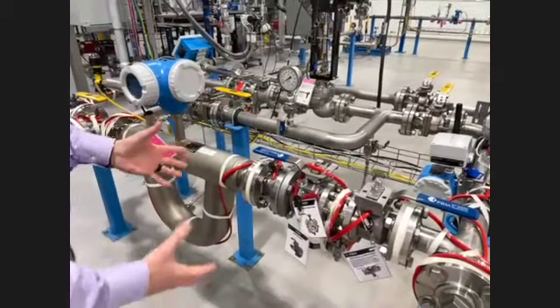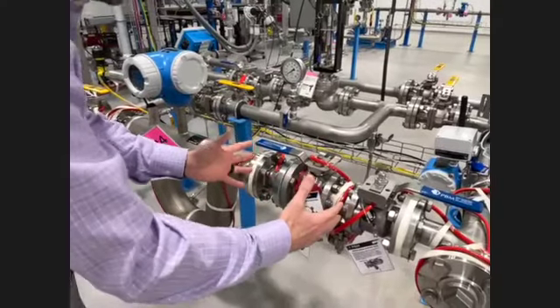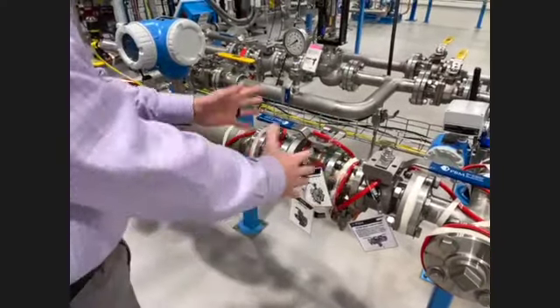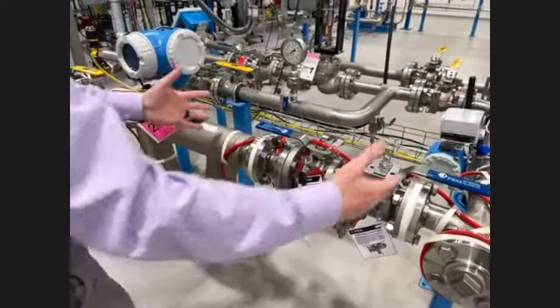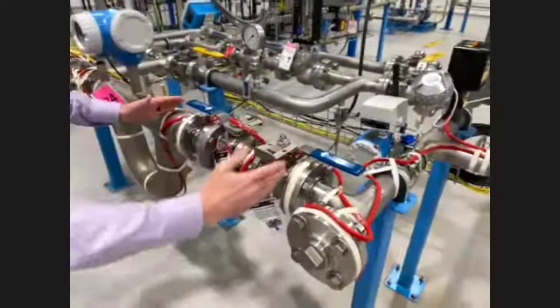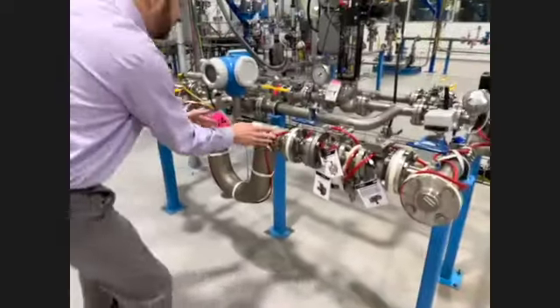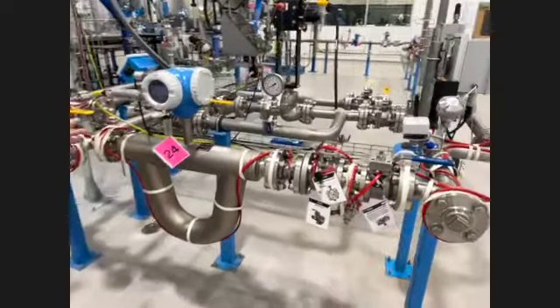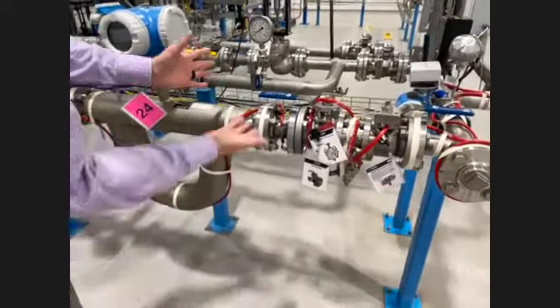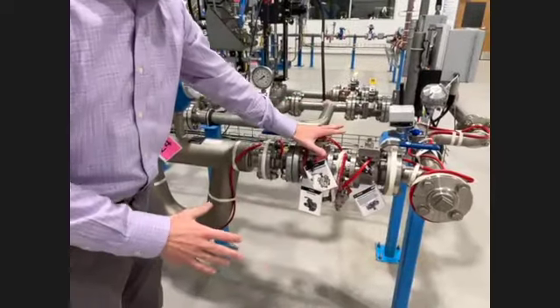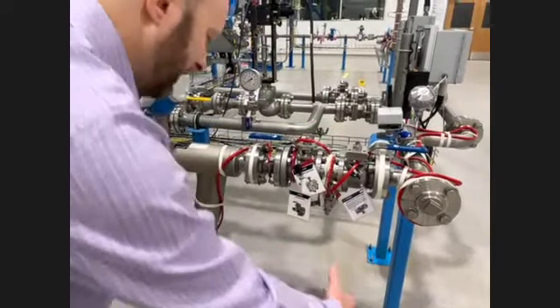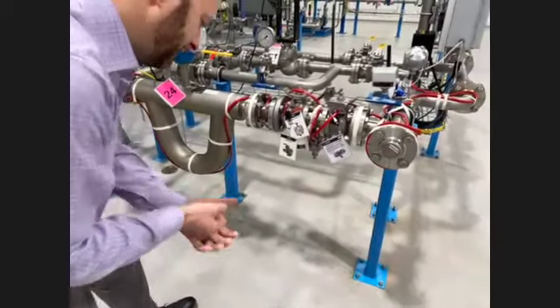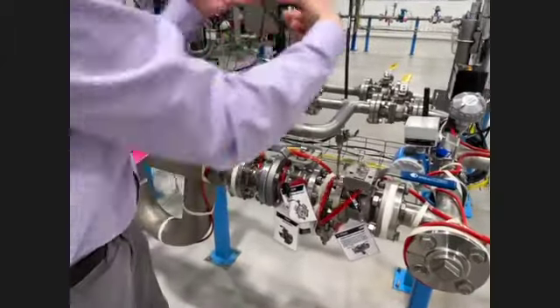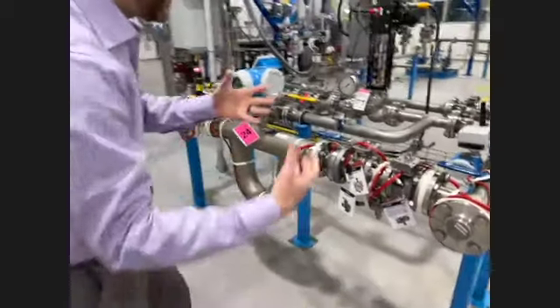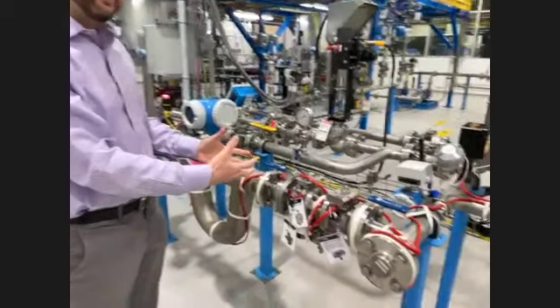So what we would do is, for example, we have a valve right here. Let's say in this application, this valve requires 8 feet of heat trace, or 6 feet, we'll say. When I'm applying my cable, I would come straight along, come down 3 feet, come up 3 feet, continue, and keep on going about my job of installing the cable. So now, if I went down 3 feet and up 3 feet, and I left that loop here, and this valve required 6 feet, there's my 6 feet. I would grab that loop, turn it into a figure 8, and then begin wrapping around it like this, kind of in a circular motion. That way you can easily do the reverse, pull that loop out of the way, and gain access to your valve. So hopefully that answers your question.